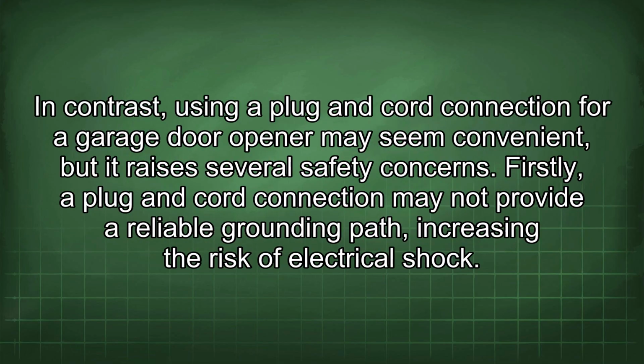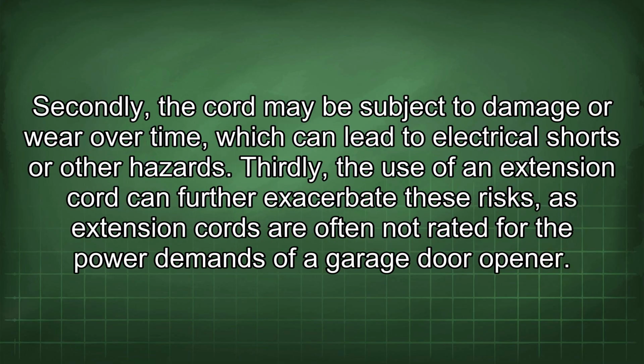In contrast, using a plug and cord connection for a garage door opener may seem convenient, but it raises safety concerns. First, it may not provide a reliable grounding path, increasing the risk of electrical shock. Second, the cord may be subject to damage or wear over time, leading to shorts or other hazards. Third, using an extension cord can worsen these risks, as extension cords are often not rated for the power demands of a garage door opener.